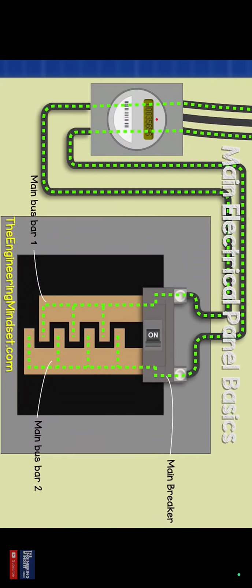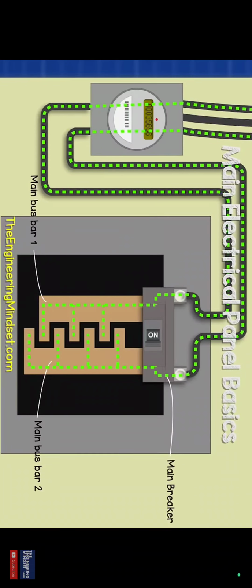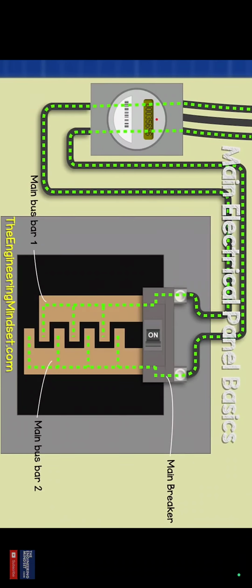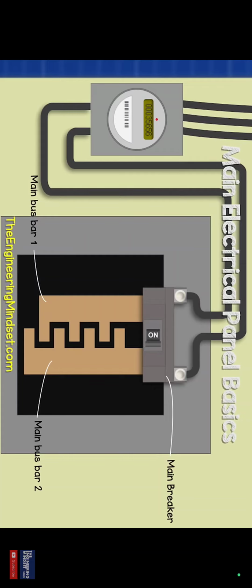Notice I've shown the current flowing backwards and forwards. That's because this is AC, or alternating current. These bus bars as well as the lugs are not insulated, they are live or hot. The main breaker can be manually flipped to cut the power to everything downstream of the main breaker. The main breaker will also provide overcurrent protection to the property.